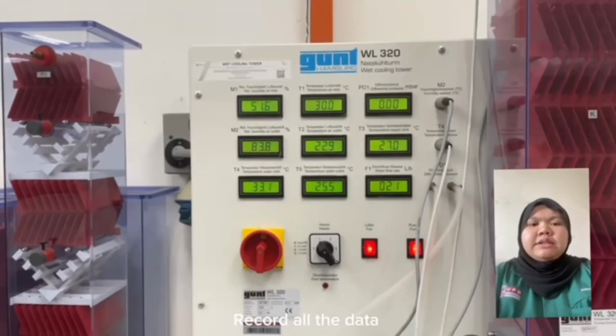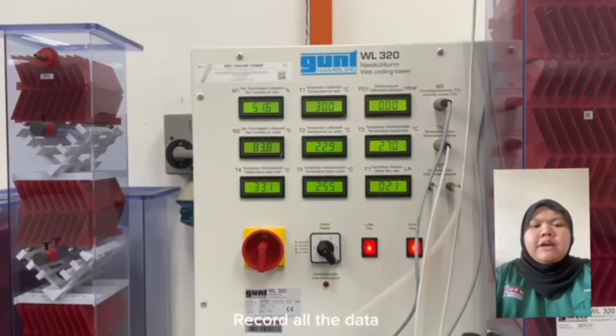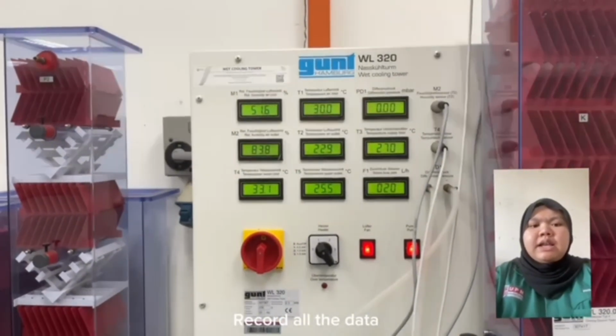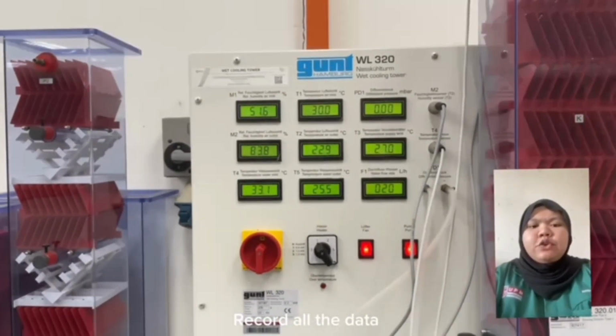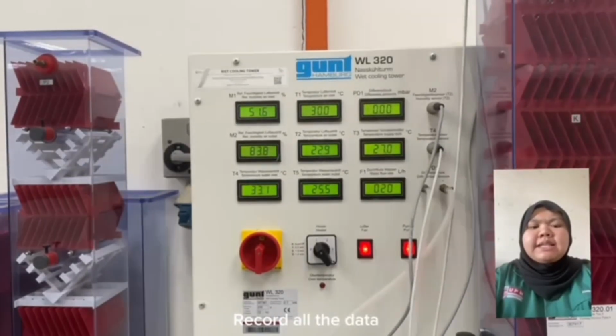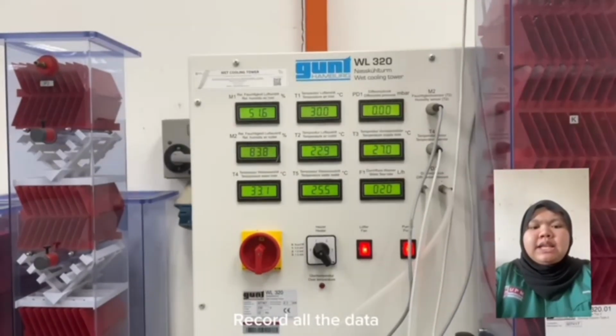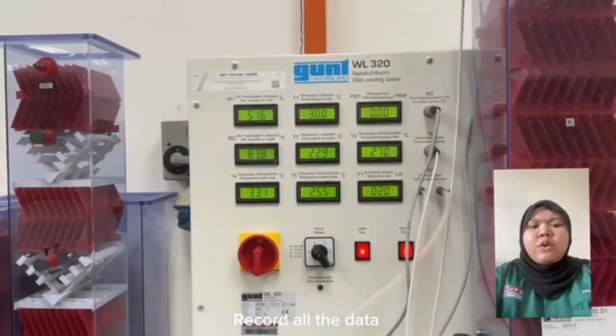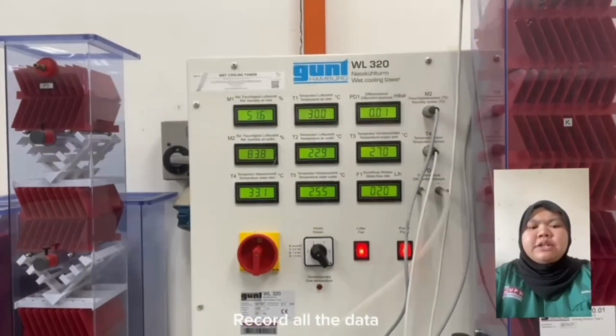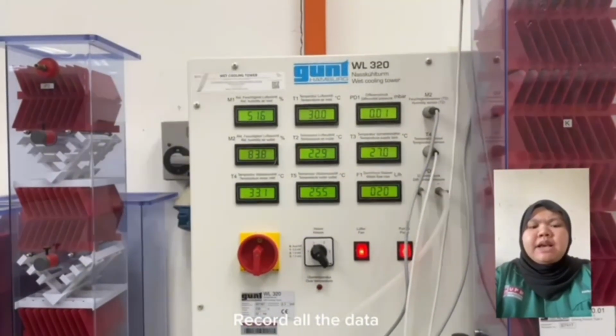After that, there are a few parameters that we need to record. First is the air inlet and outlet temperature, relative humidity for inlet and outlet, supply tank temperature, water inlet and outlet temperature, water flow rate, and differential pressure. Lastly is makeup water quantity.